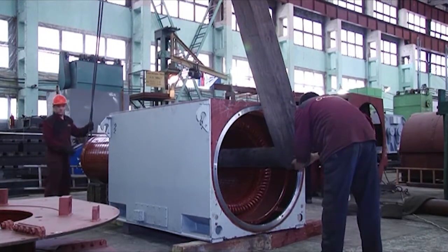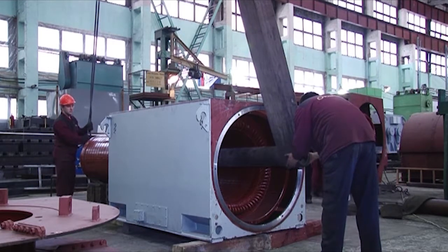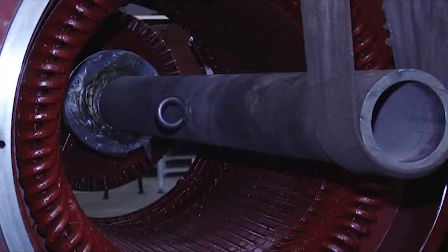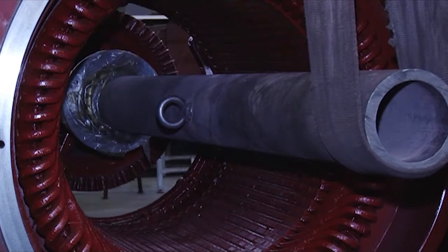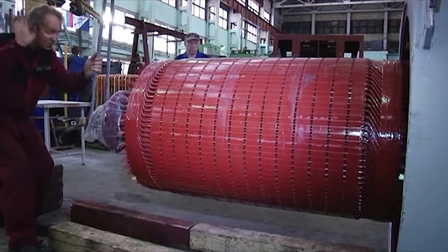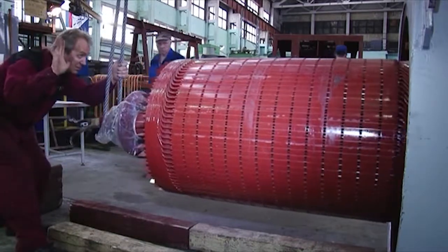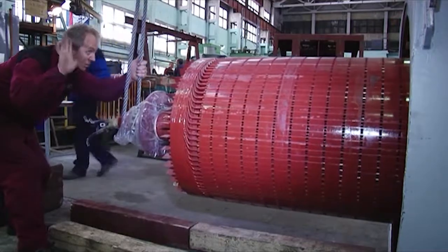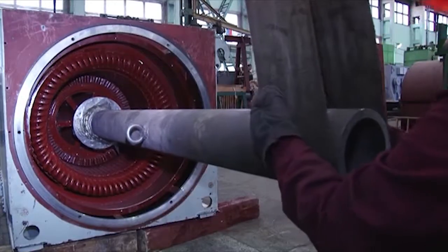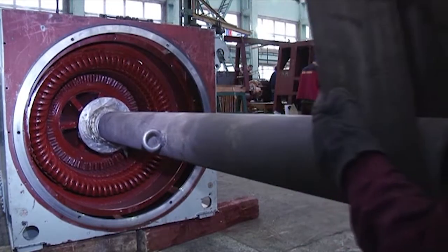The final stage of the motor assembly is the rotor installation into the stator. In the case of large electric motors which are used at hydraulic power plants, this operation may require several hours. This is to be carried out with the utmost care to avoid damaging the stator winding.